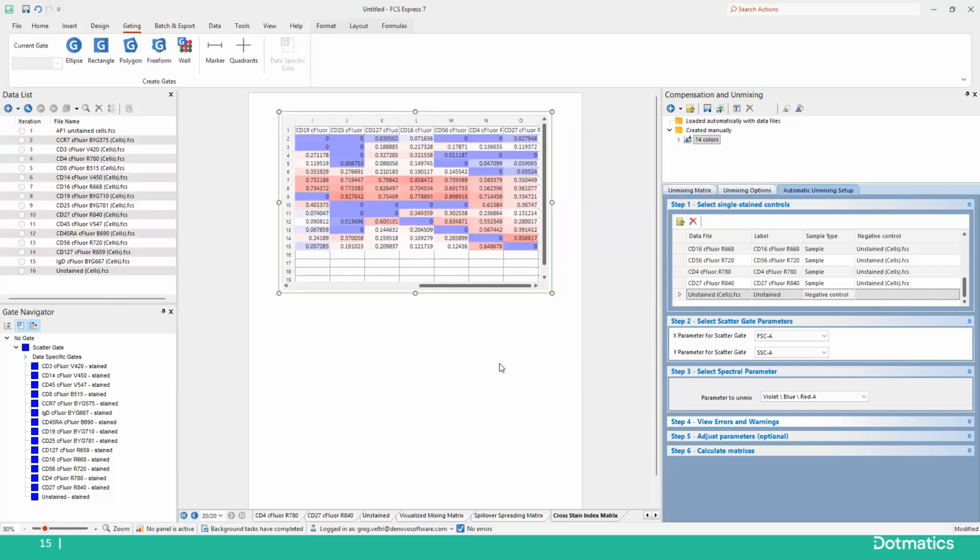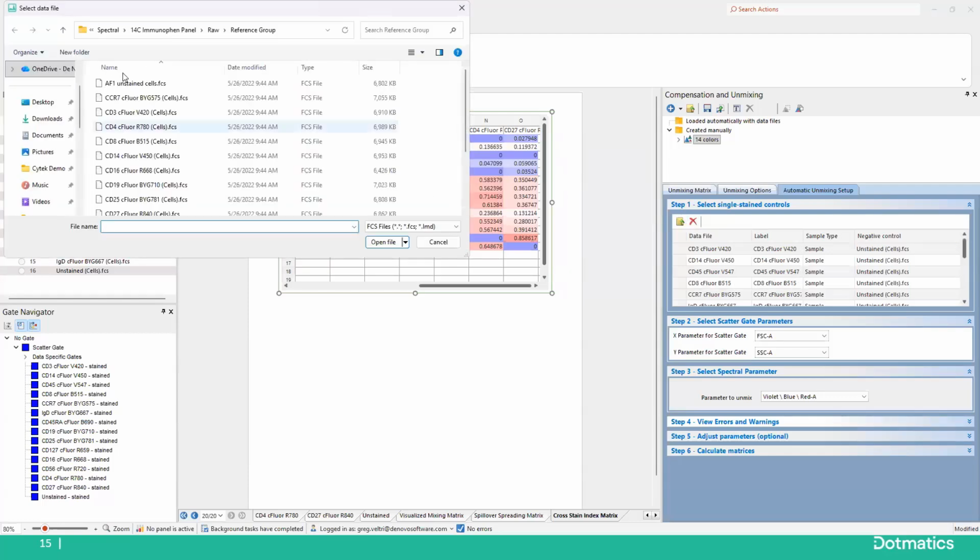All right. Now, for your autofluorescence that someone asked about, I can also have an autofluorescence sample. What that means is that my unstained is going to be used to do the subtraction to find the spectral, but the autofluorescence is another spectral color that may cause problems in here. Now, this is human peripheral blood. You don't really see the difference, and I'm going to show you in a second why that is, but this is the best example I could have for today.